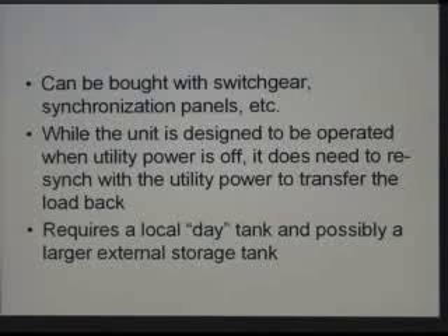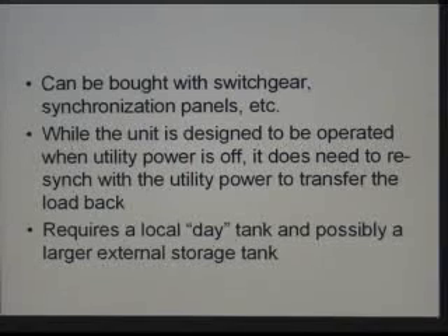So in case of power failure, does the generator auto start, or do you have to manually push the button? You can set it up either way, but generally they're set on auto start. What the signal normally is, when utility power drops, the breaker that ties the emergency bus to utility power, as soon as that opens, that gives a signal to the diesel genset to start. That way you don't accidentally start it when the utility power is still on.